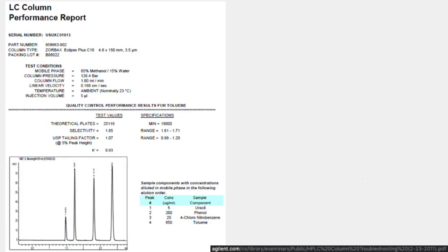Let me show an example now of what you might do with this. This paper is the best example I could find on the internet of a column acceptance report or certificate of analysis. It basically shows you when you buy a column, it shows you that someone tested it, and then it works. Because these things are $500 to $1,500, you would hope it works. They test them at the factory before they send them to you, and they give you the results from the test in the box with the column, which is super useful. The pieces you have here are the conditions. A lot of these numbers and your chromatogram will change if you change the temperature. So the temperature is shown there, your flow rate is shown here, your solvent system is really important, so that's shown. Those details are necessary to be able to describe what you're doing.